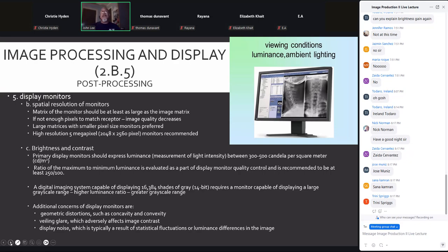For brightness, the primary display monitors should express a luminance between 300 and 500 candela per square meter. The ratio of maximum to minimum luminance is recommended to be at least 250 to 100. 14-bit digital imaging systems are capable of producing 16,384 shades of gray. And so this requires a monitor that will be able to display at least that many shades of gray.